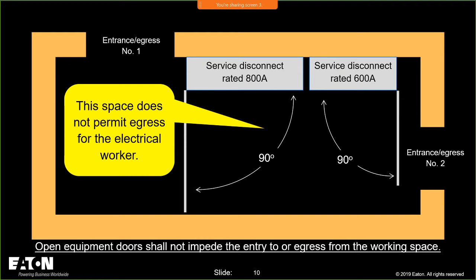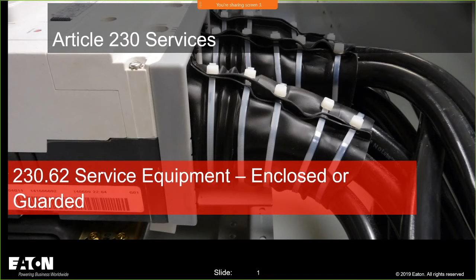So that was 110.26, working space about electrical equipment, a big change. Now let's take a look at 230.62, service equipment, enclosed or guarded. This is where we get into the booties on the breakers, the barriers. This is all about shock protection, focused on keeping our electrical workers safe.